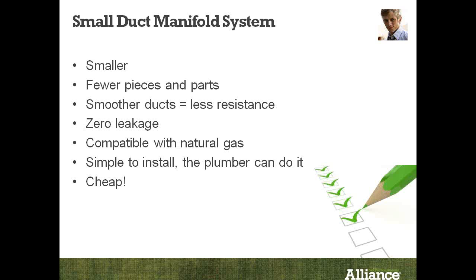These smoother ducts have less resistance, and so that helps with efficiency. They have zero leakage, which again has many benefits. And this system is frankly compatible with natural gas. And so, in different cases, natural gas is definitely the preferred fuel, and there's no reason that these systems can't be used with that. And these systems are dead easy to install.